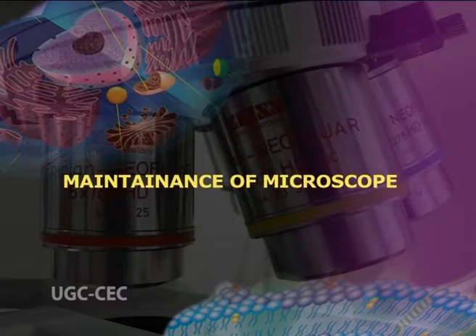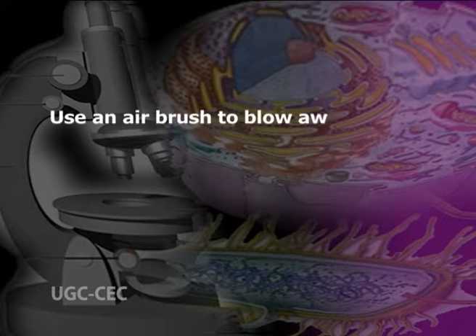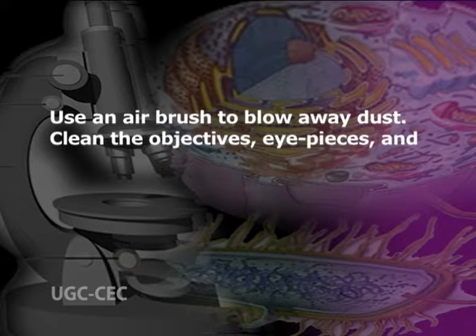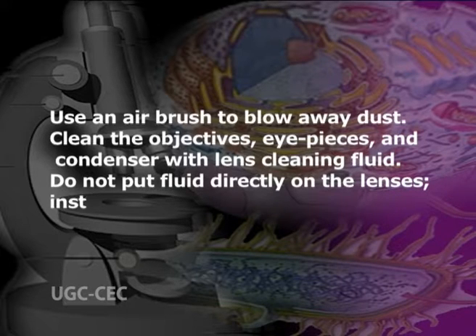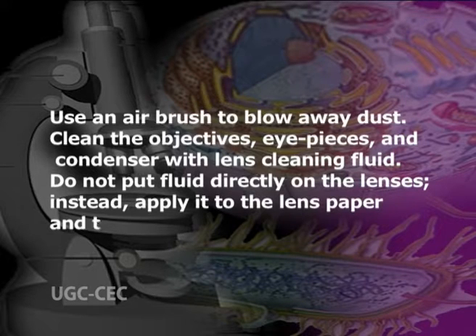Maintenance of the microscope: every month, use an airbrush to blow away dust. Clean the objectives, eyepieces, and condenser with lens cleaning fluid. Do not put fluid directly on the lenses; instead, apply it to the lens paper and then clean. Remove the slide holder from the mechanical stage and clean with tissue moistened with water. Wipe the dust off the body of the microscope and the window of the illuminator in the base of the unit. Every 6 months, thoroughly inspect, clean, and lubricate the microscope after consulting the manufacturer's manual. This should preferably be done by professional service personnel.